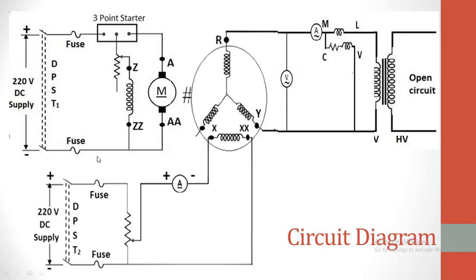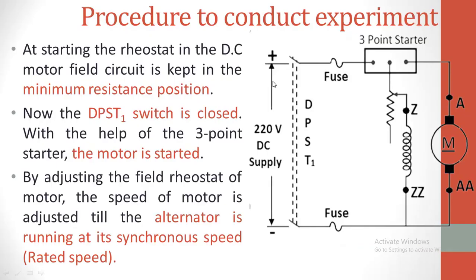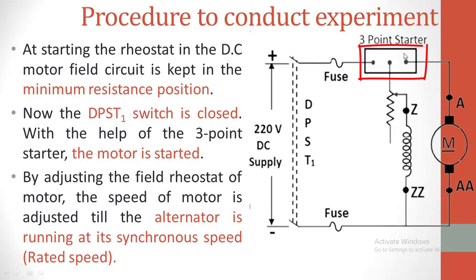First we will discuss for motor and next we will discuss for the generator. This is the motor circuit: DPST switch, three-point starter, rheostat placed in the field circuit, and this is the armature circuit. At starting, the rheostat of the DC motor is kept in the minimum resistance position. The DPST switch is closed, and with the help of the three-point starter, the motor is started.